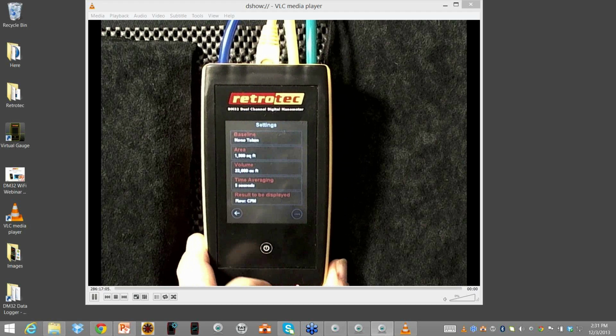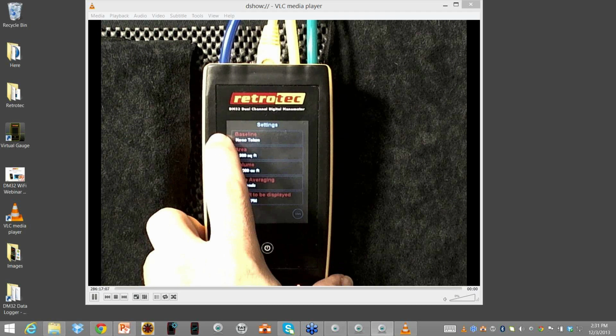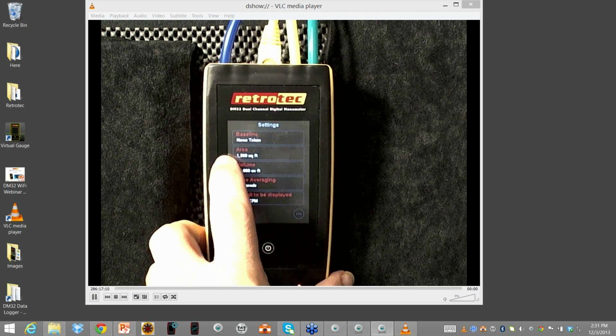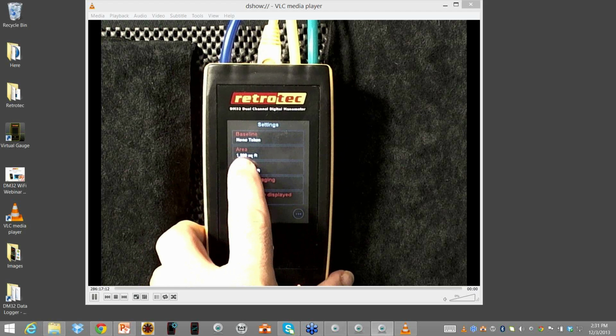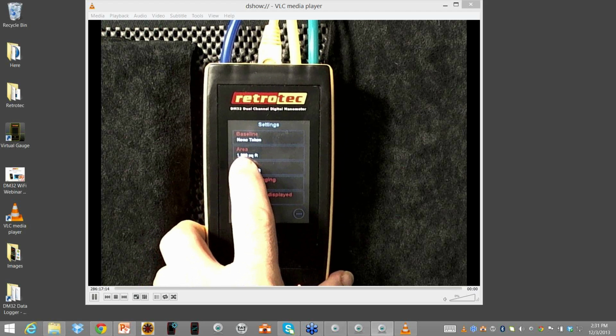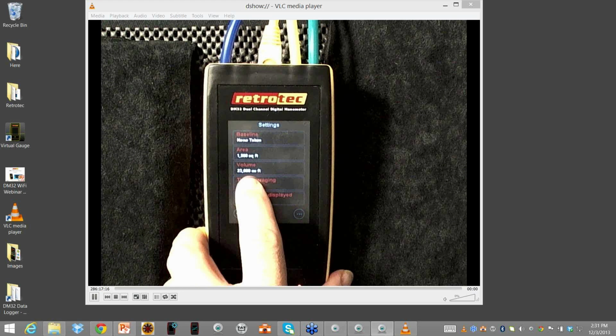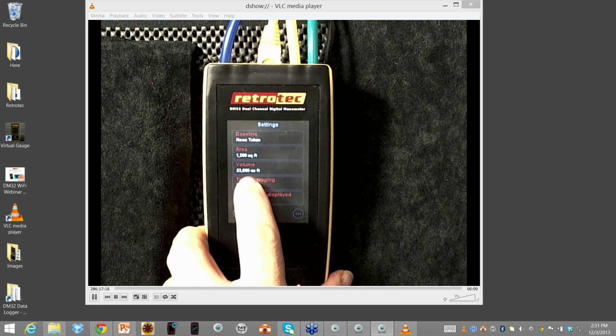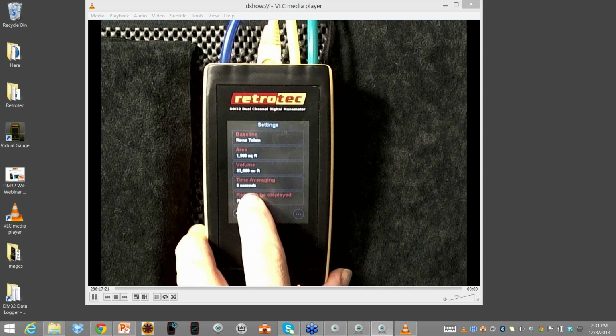I'll show you how to do a baseline real quick. The area and volume are right here, and that's what determines whether I want CFM per 100 square feet—this is the square footage I'm using, or the volume. If I'm doing air changes per hour, here's the volume I use, and here's where I change the time average. The results are displayed the same way when I hit channel B.